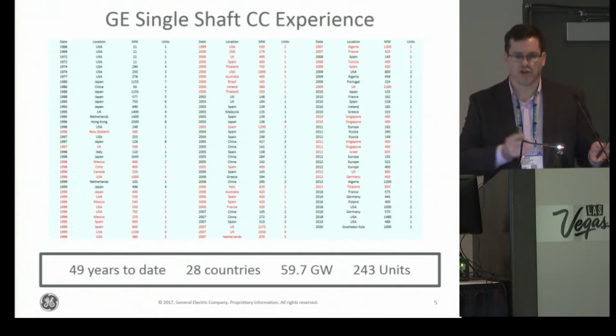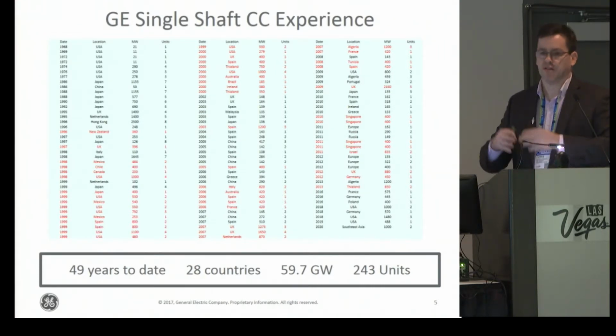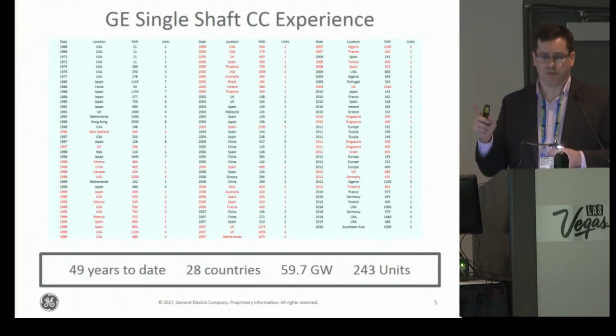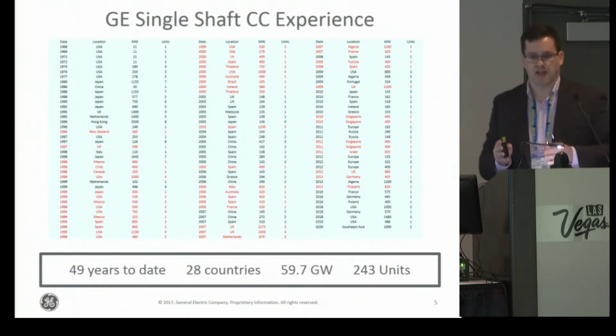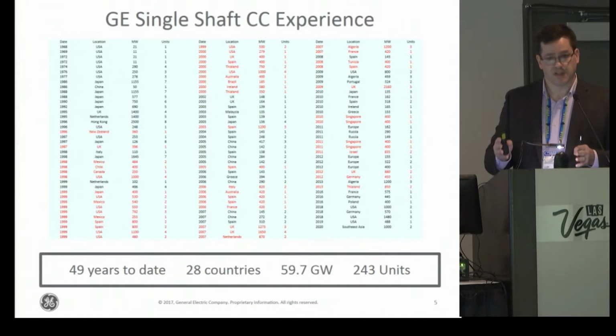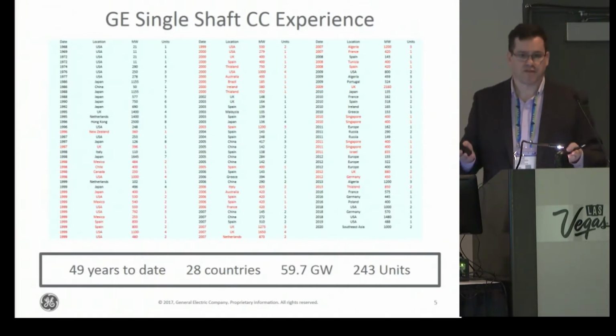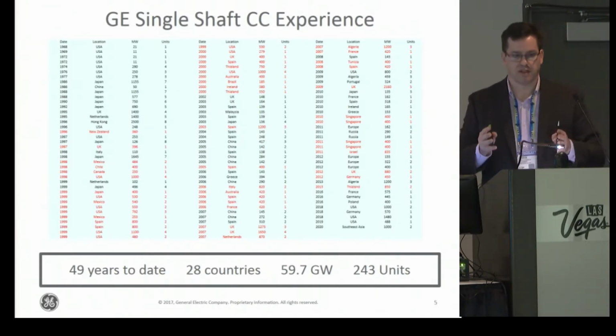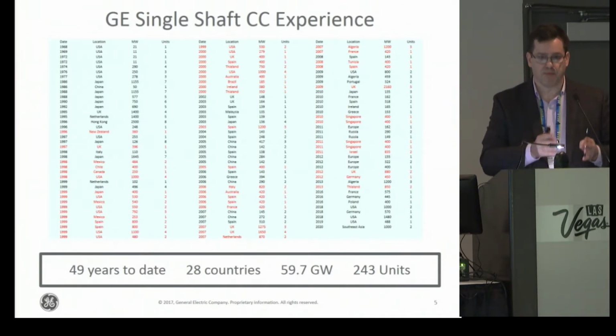Previously, when you looked at multiple single shafts versus a multi-shaft combined cycle plant with one steam turbine, the multi-shaft combined cycle plant would have a significant efficiency advantage, about half a point of efficiency. That was because the larger steam turbine was more efficient than a bunch of smaller steam turbines.